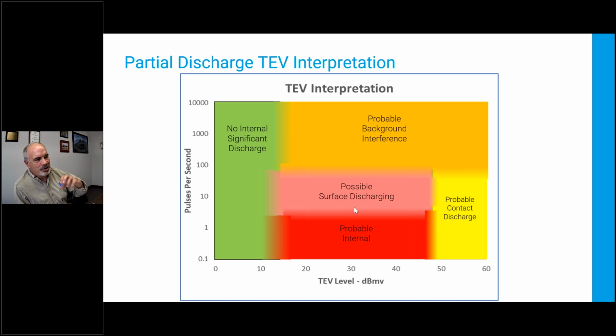Now, if you talk about surface discharge, where I have this treeing, and every branch on that tree can fire at a slightly different voltage, I can get multiple pulses per cycle, more than 4 to 6. I can get 10, 15, 20 in one cycle. So I would say that this is in the area of surface discharge. Got a really low level, I'd say that's nothing significant. If I've got a really high pulse per cycle count, then that tells me I'm probably listening to some sort of interference. Radio waves, fluorescent lights, various different things can create background interference.